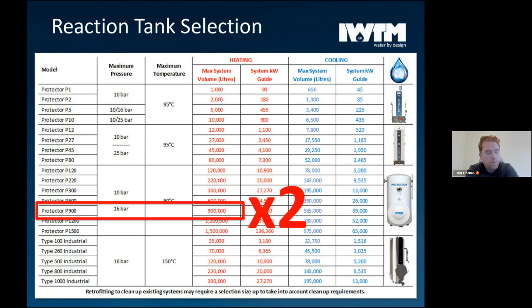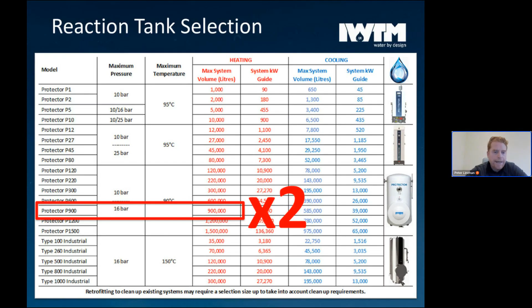The protector can work in multiple different pressure ratings, up to 16 bar, even higher if needed. We have a maximum temperature of up to 150 on these industrial units, which is what we use in our marine industry. But some of the astute will notice that our largest protector unit is a P1500, which can only treat 1.5 million litres, which isn't enough to treat this system. That's not a problem, because you can multiply the number of units on a system to surpass the system volume limit. So what we chose for this system was 2 protector P900s, which together will be able to treat 1.8 million litres of LTHW system. So it's very simple and easy to select our units for your system volumes.